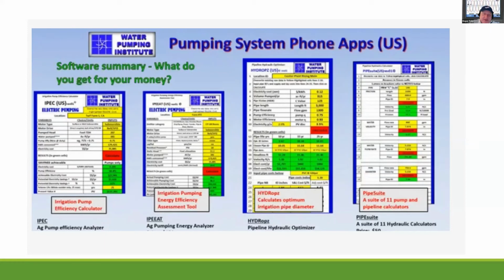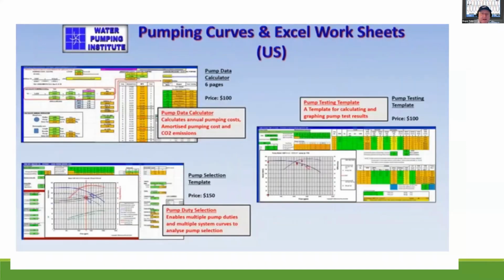One thing we had talked about is that there are additional savings sometimes once you get all of this down, where you might just want to slow the whole hydraulic system down, get it back to best efficiency for the pipe, and also for your pipe calculators, and all your pressure regulators and head pressure through valves, through filters and all those things. And that's what he goes into in his master class.